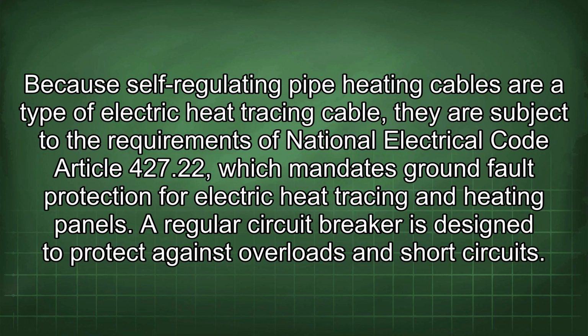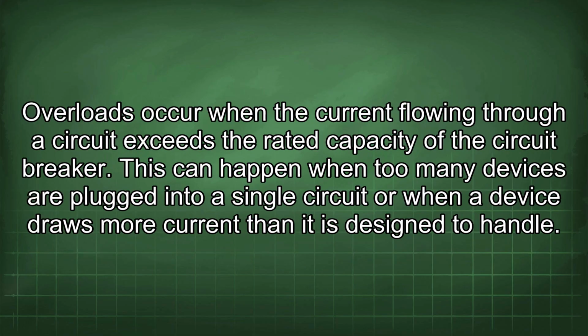Because self-regulating pipe heating cables are a type of electric heat tracing cable, they are subject to the requirements of National Electrical Code Article 427.22, which mandates ground fault protection for electric heat tracing and heating panels. A regular circuit breaker is designed to protect against overloads and short circuits. Overloads occur when the current flowing through a circuit exceeds the rated capacity of the circuit breaker. This can happen when too many devices are plugged into a single circuit or when a device draws more current than it is designed to handle.